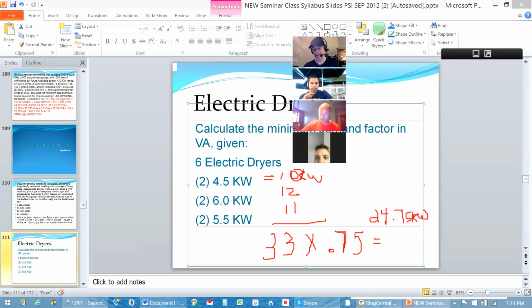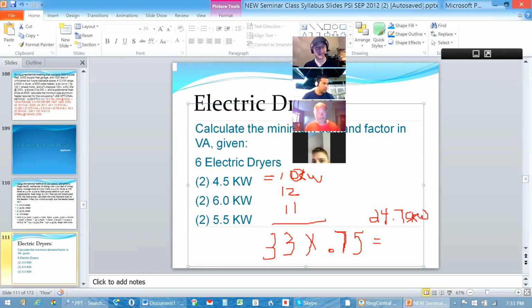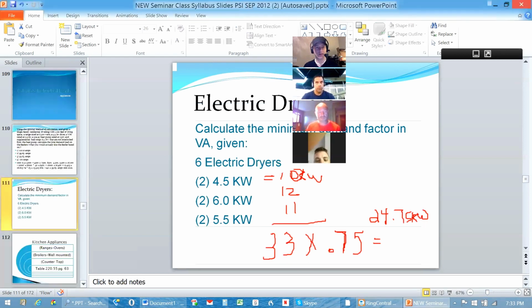So if I were to have, let's say, 41 dryers, and I'm asked to size the neutral for 41 dryers. This is one that was pretty common for a while, and then it kind of disappeared, and then it came back, and I can't tell you honestly if it's still there or not. But you took your test not too long ago, Robert. Do you remember any big dryer questions like 21 or 18 dryers or 41 dryers, something like that?